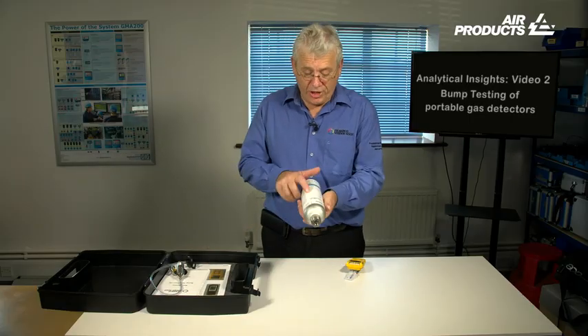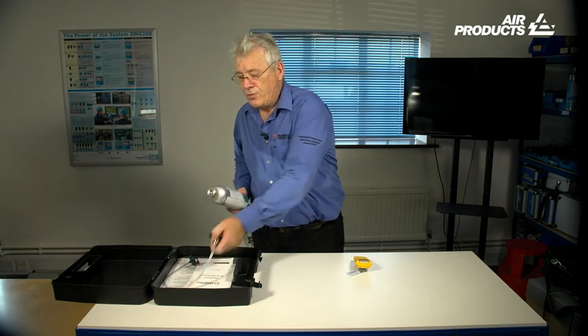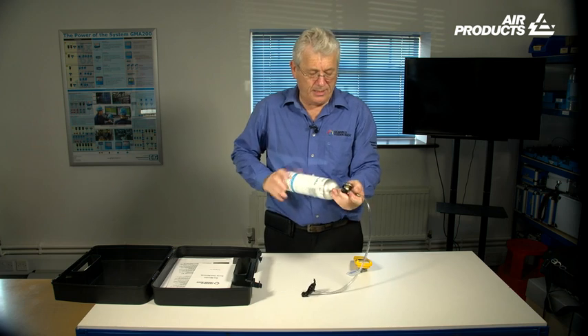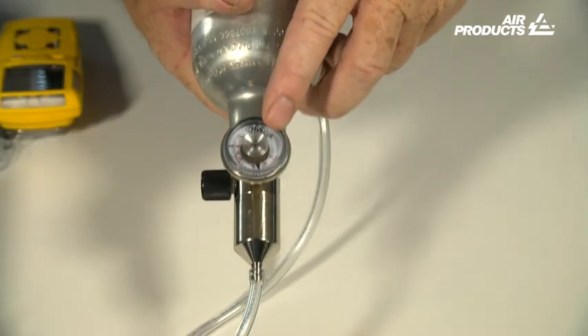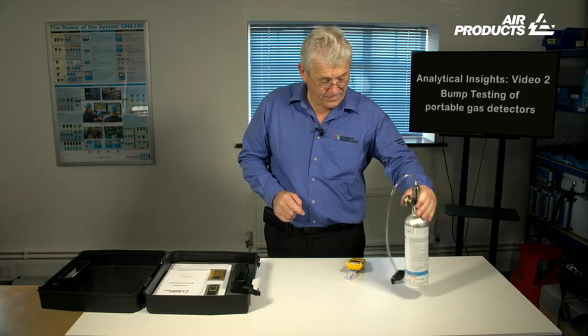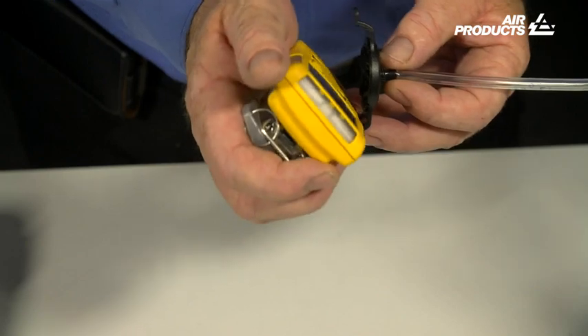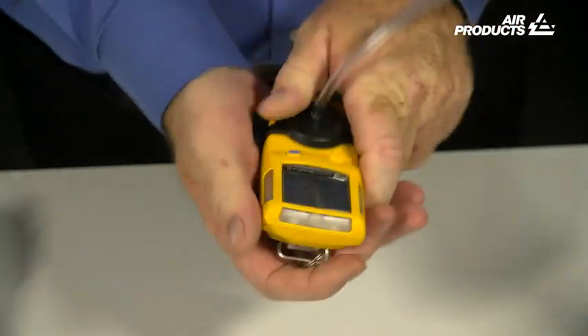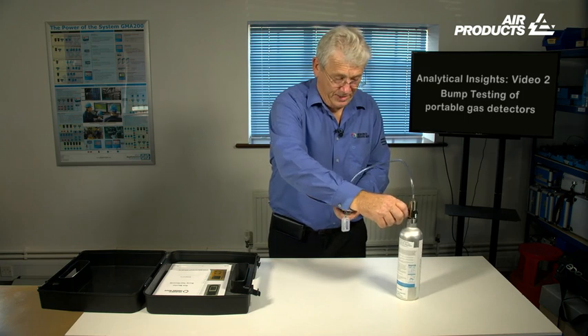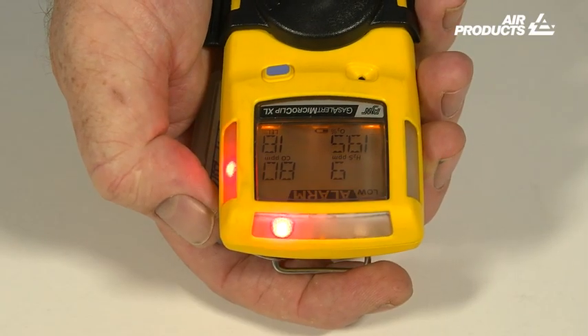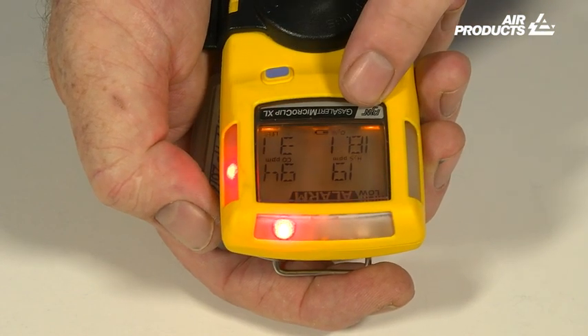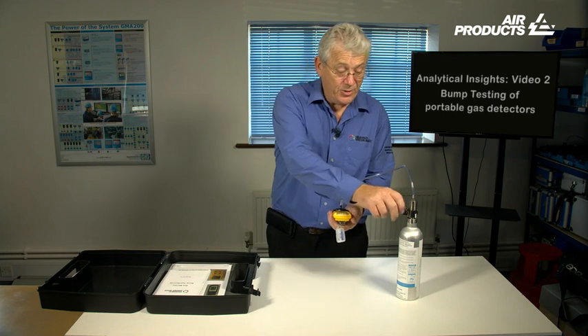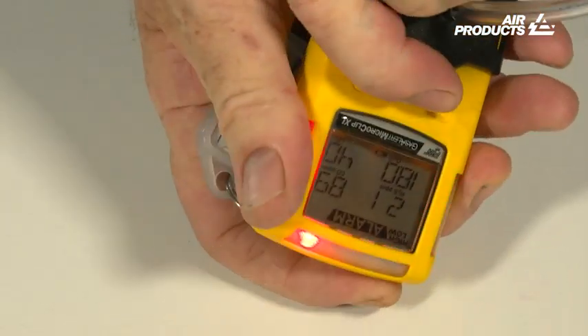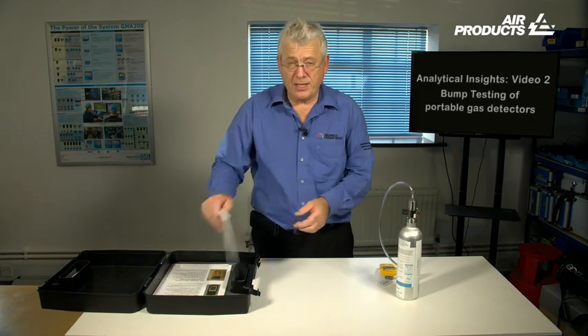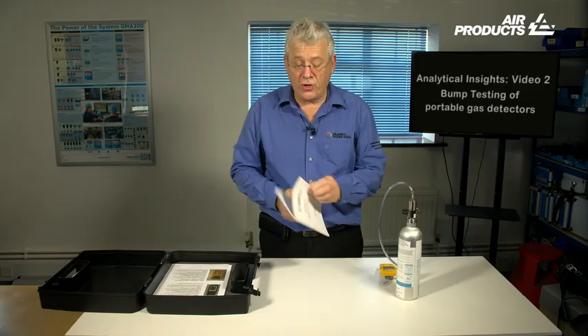Take your gas bottle out, check that your date is within calibration. Take your regulator, screw it onto the end of the gas bottle. Ensure you have gas reading. Take the clip and attach the clip to the device. Introduce gas slowly and check all 4 sensors are alarming. Once that's happened, turn the gas off, disconnect the clip and allow the monitor to clear. And finally, the most important part, take the bump test record book and record the bump test.